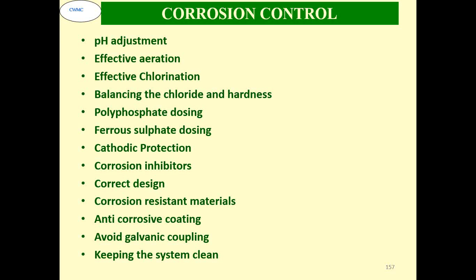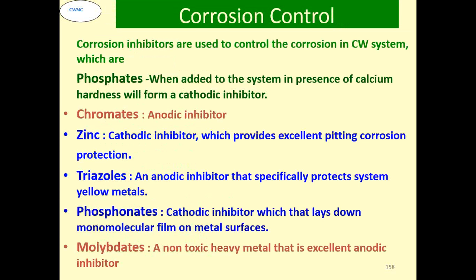What are the general corrosion control measures? You adjust the pH, effective aeration, effective chlorination, balancing the chloride and hardness, polyphosphate dosing, ferrous sulfate dosing for the seawater system, and having brass or copper based systems. Cathodic protection, corrosion inhibitors, correct design, use of corrosion resistant material, using anti-corrosive coatings, avoiding galvanic couplings, keeping the system clean. That's the important thing.